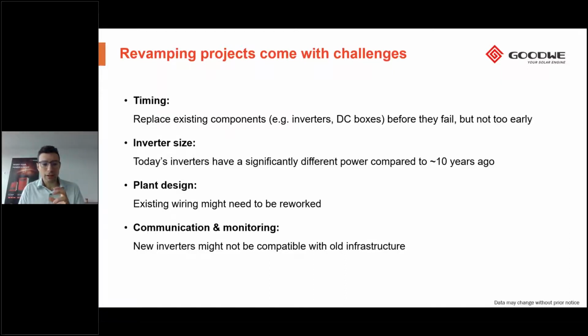If we bring it specifically to the inverter, a very big challenge for these power plants is that today's inverters have significantly different power compared to inverters offered 10 years ago. What used to be a central inverter in the past, typically starting from 200 kilowatt, going up maybe to 630 kilowatt, is now much smaller than any existing central inverter on the market. It rather matches the string inverter size, but still, any change of the inverter comes with a lot of challenges. It might require the whole power plant to be rewired. Also, the communication and monitoring might not be compatible with the existing infrastructure when we bring new inverters. So, not an easy topic, but a very interesting one.